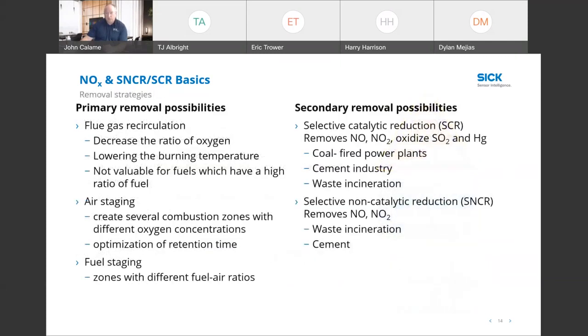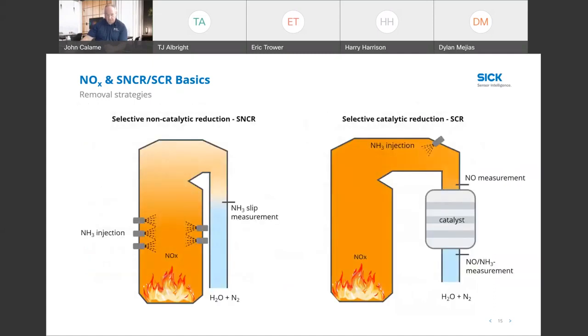So there are several removal strategies. The ones that we're really going to focus on today are the SCR, selective catalytic reduction, and the SNCR, selective non-catalytic reduction. But there are other ways to remove or mitigate NOx, such as low NOx boilers, increasing the combustion efficiency to make sure that you're not in a fuel-rich situation. So there are multiple ways to mitigate the NOx, but whatever strategy you use, you still have to measure the effectiveness of that and meet your permit requirements via the EPA guidelines or state guidelines.